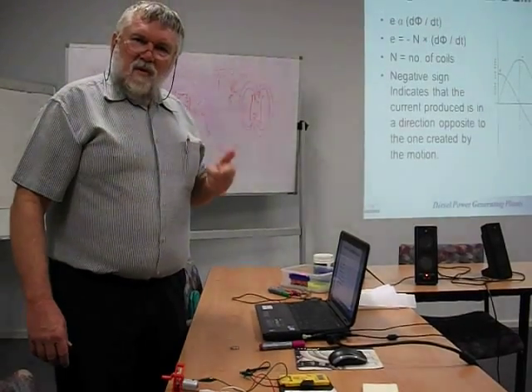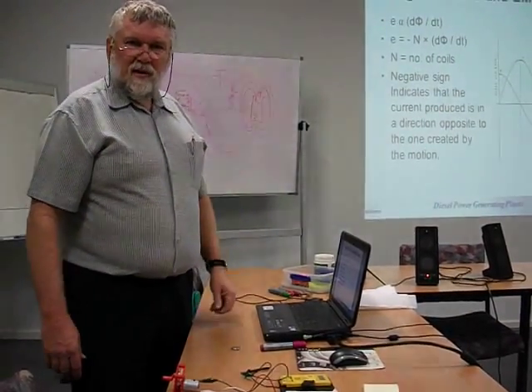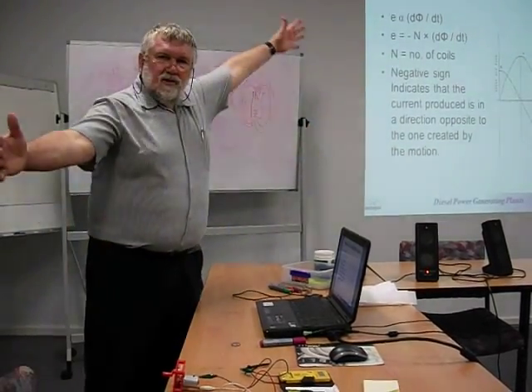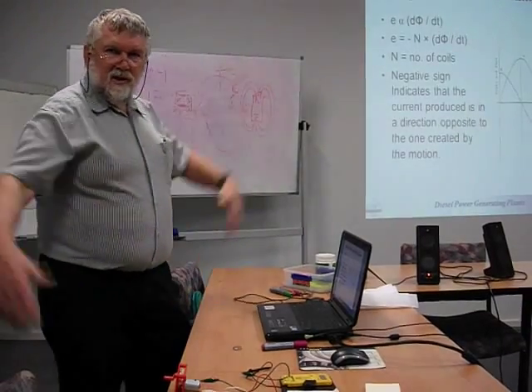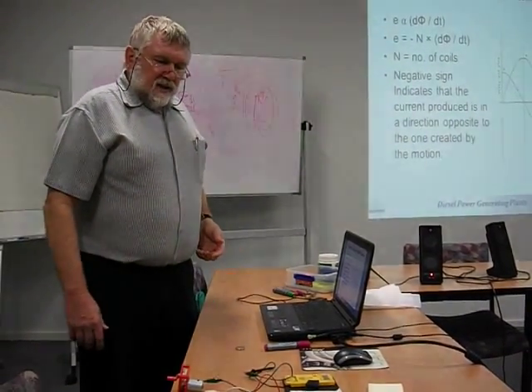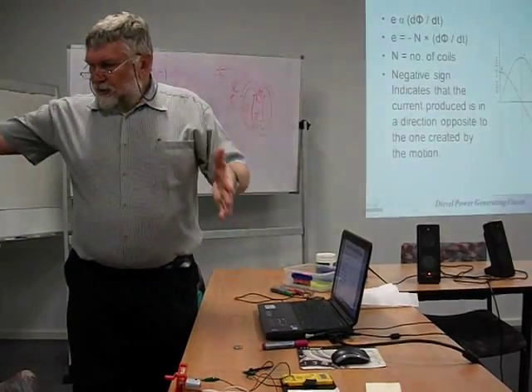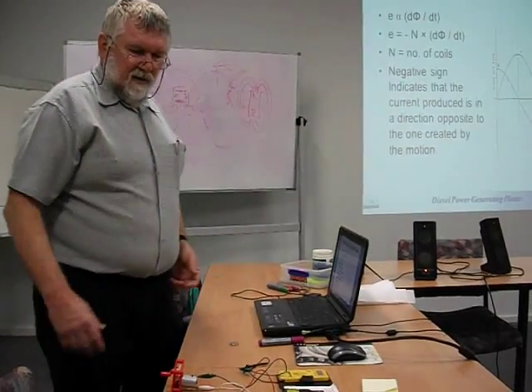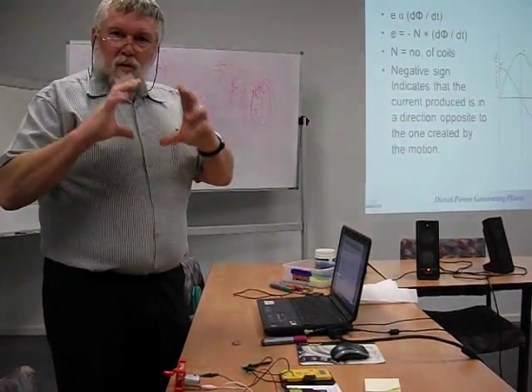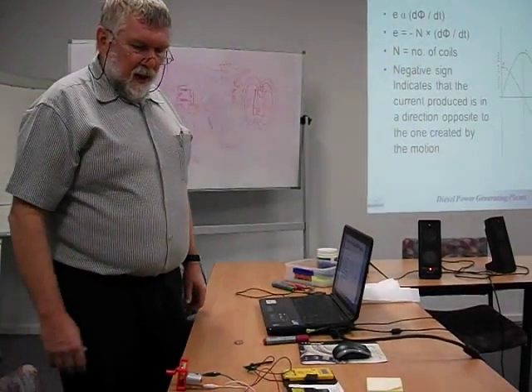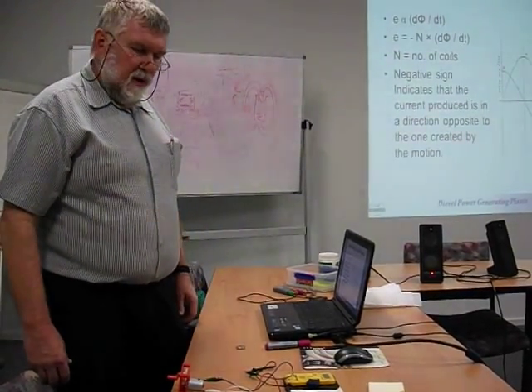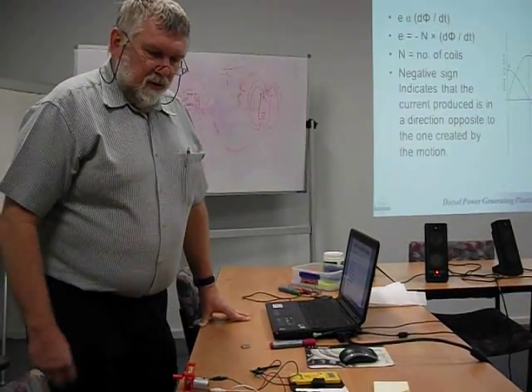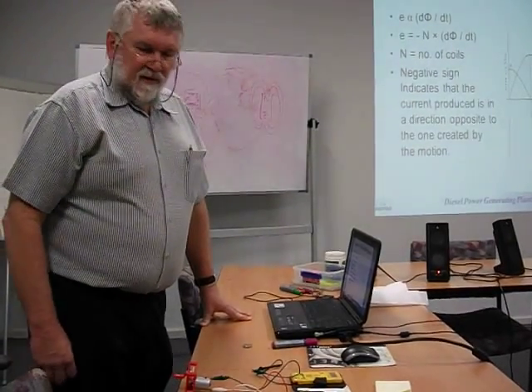And the magnetic forces involved are absolutely staggering. They're enormous. You look at the size of an engine, you know, it's 20 feet long, a 20-cylinder engine or something like that. And it's plugged into a generator that might only be four or five feet, a meter, meter and a half long. And that's taking all the power that the big diesel can deliver. So the forces to transmit that power, and it's all transmitted through the magnetic fields, those forces are very large. So the structural side of our generators is very important as well.